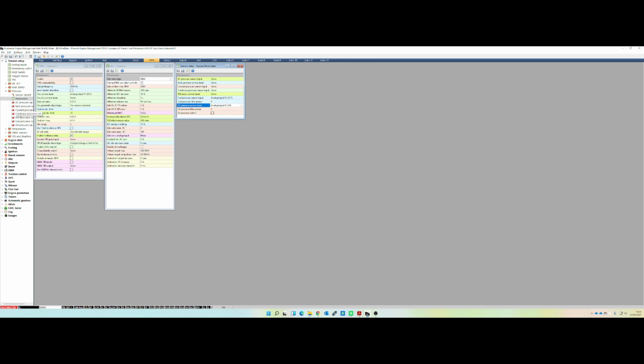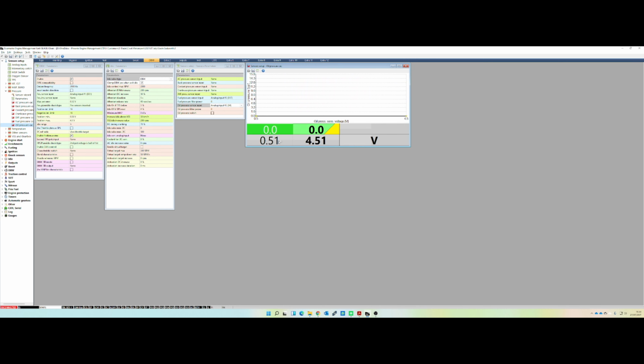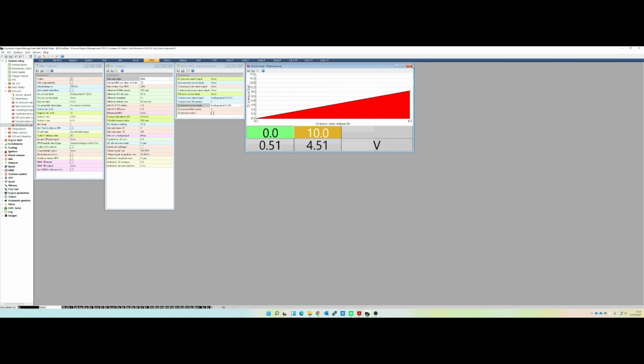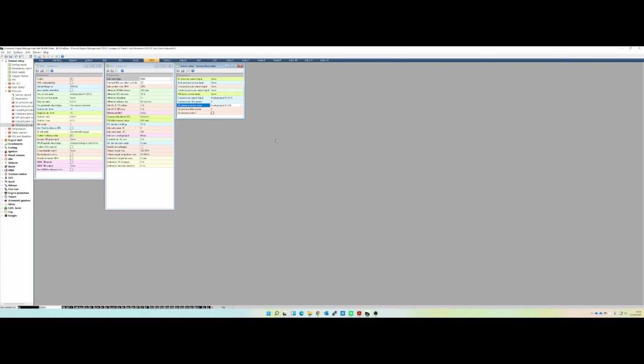These ones down here are how you set up your oil pressure calibration. These values seem pretty standard for people who've set this up before. For instance, if you had a 150 psi sensor, which is about 10 bar, 0.5 volts would be 0, and 4.5 volts would be 10 bar. Nice and simple, easy to do - just get the settings from your particular sensor and input those over there.